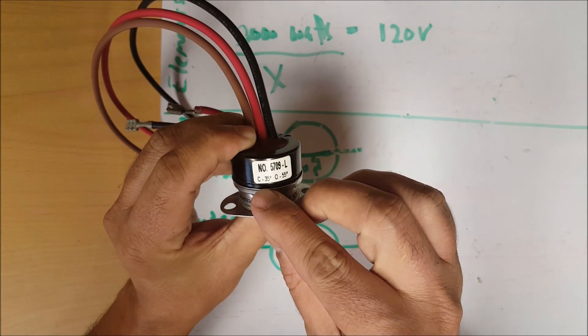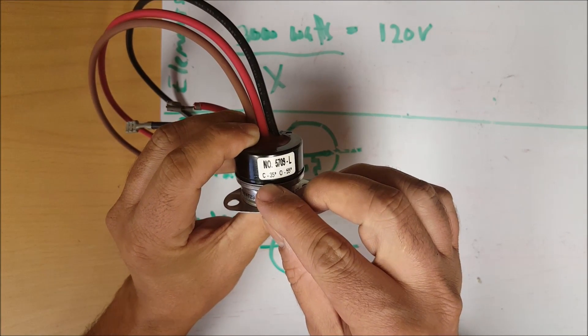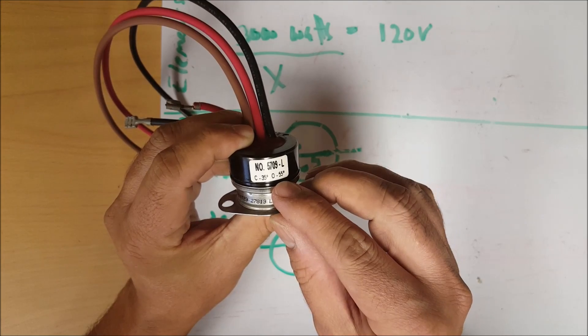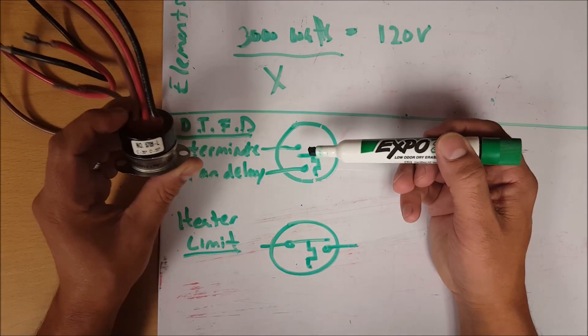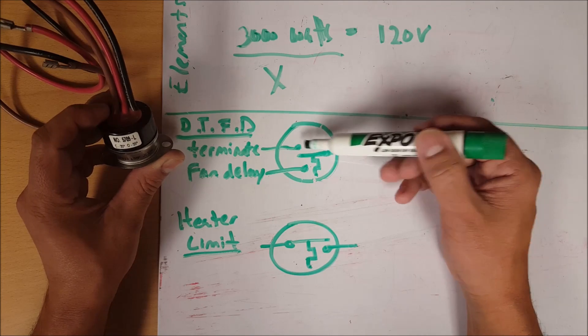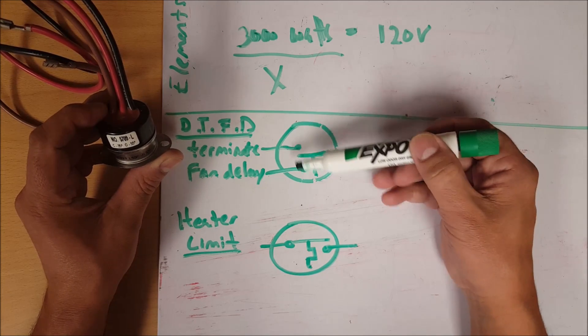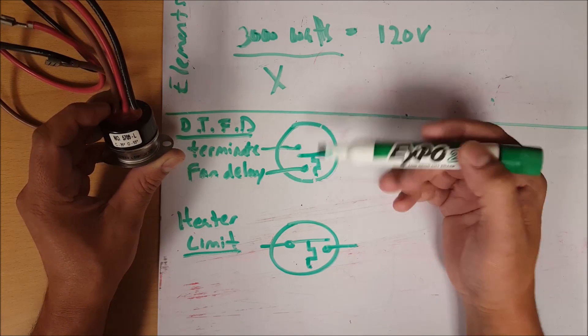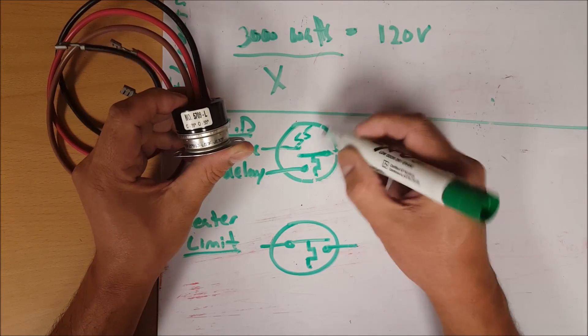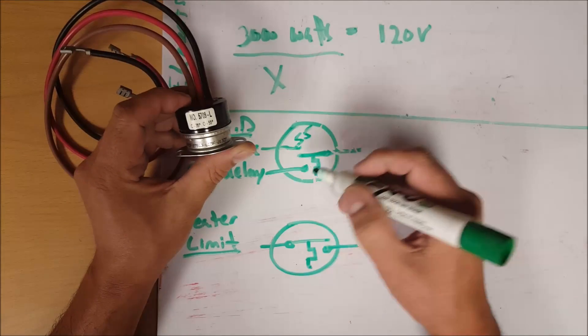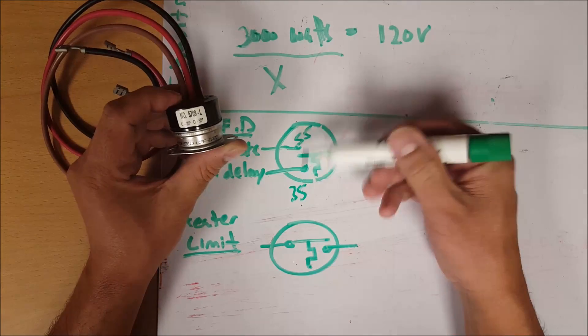So this is representing that it closes at 35 degrees and opens at 55 degrees. We have basically two switches in one. On temperature rise this side will close. On temperature fall this side will close. So based on these specs, at 55 degrees this side will close and at 35 degrees on this end this side will close.